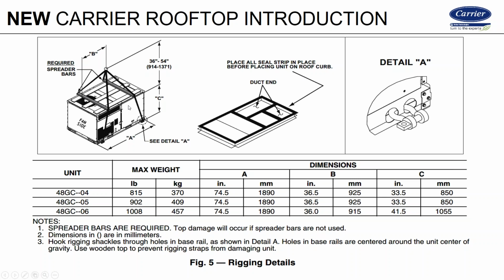Additionally, now you're going to see on the units a sticker that says you must use spreader bars. So think about this piece of wood slat right here as a spreader bar, if you're not familiar with that. This crate always needs to stay on top of the unit until it's lifted by a crane or helicopter and set in place. If you take this crate off and you don't use a spreader bar, what happens is a single point pull takes these straps and breaks them over the edge, and you end up wrinkling and denting the edge of the unit on all 4 sides. So there's stickers now to say you must use spreader bars.